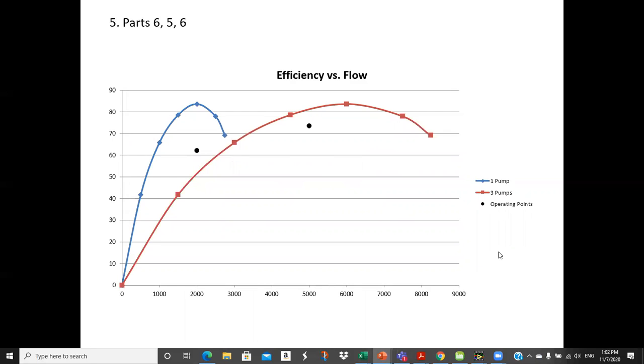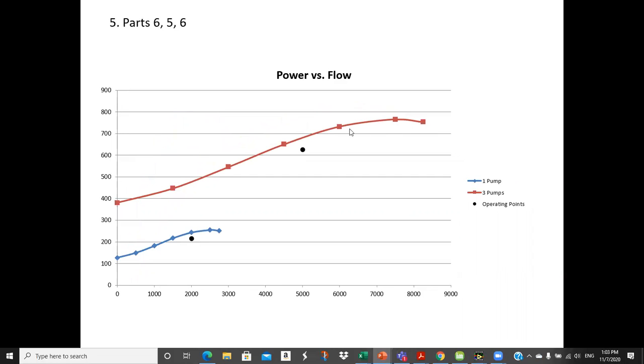Okay, when I check efficiency, this is just a plot of the efficiency versus flow for the 1 pump and then for the 3 pumps. And then these are my operating points, and you can see I'm not quite up to snuff. I mean, 3 is doing better, so it could be just one of these pumps is degraded. But it probably would require some investigation. And then here is the flow versus power curve, and you can see we're not using quite the power that would be projected, which would be an indication that maybe impellers are damaged or clearances have opened up.